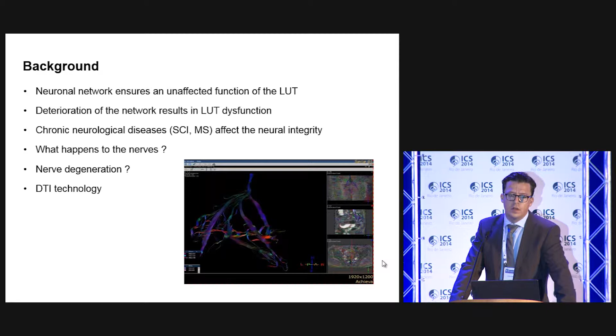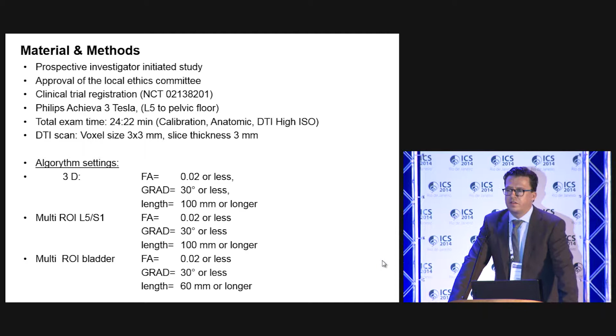For the materials and methods, it was a prospective investigator-initiated pilot study. We got the ethical approval. We used the Philips 3 Tesla MRI for this investigation. The total scanning time was 25 minutes, including calibration, the anatomical scan and the DTI high ISO measurement. We used a voxel size of 3 by 3 millimeters with a slice thickness of 3 millimeters.